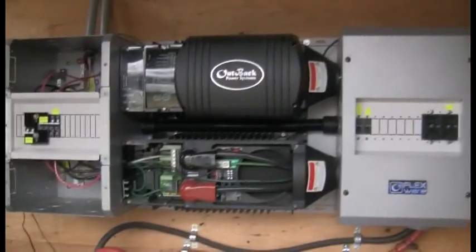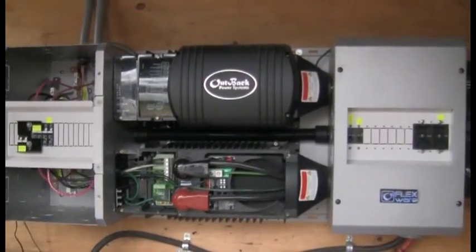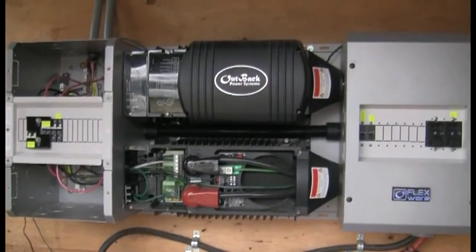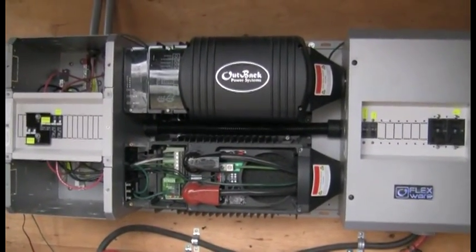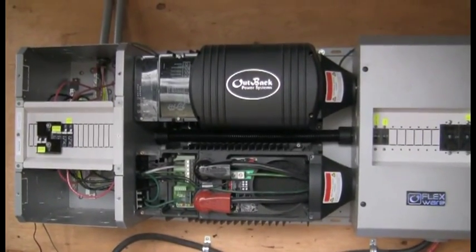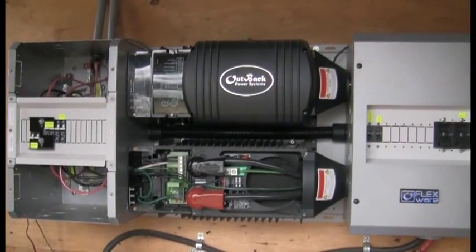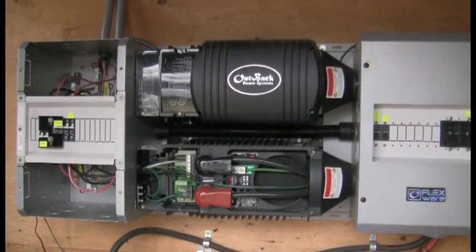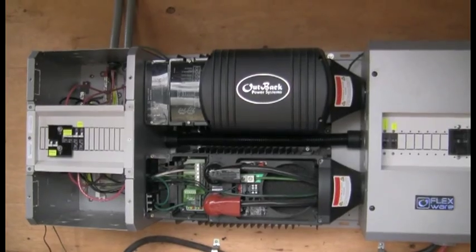I've programmed these inverters to run in what's called a classic stack configuration, meaning each inverter is responsible for each hot leg in a 240-volt split-phase system. It's capable of running in 240-volt mode when both legs sense load but is equally able to service 120-volt loads on each appropriate leg.